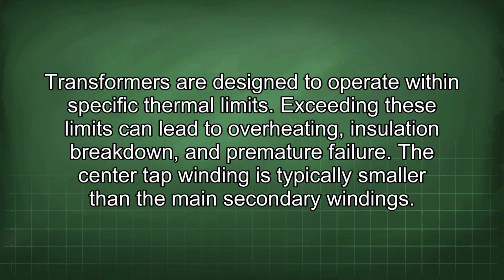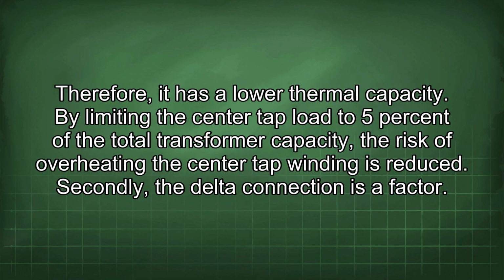Transformers are designed to operate within specific thermal limits. Exceeding these limits can lead to overheating, insulation breakdown, and premature failure. The center tap winding is typically smaller than the main secondary winding. Therefore, it has a lower thermal capacity. By limiting the center tap load to 5% of the total transformer capacity, the risk of overheating the center tap winding is reduced. Secondly, the delta connection is a factor.